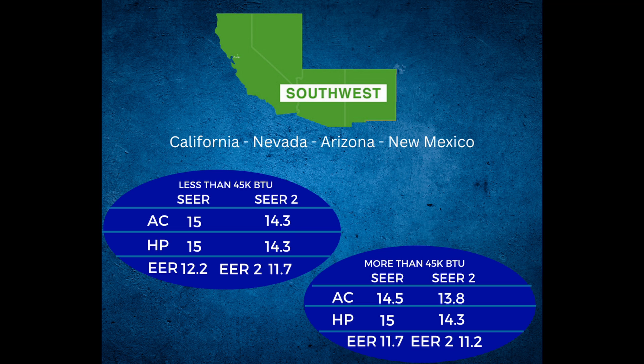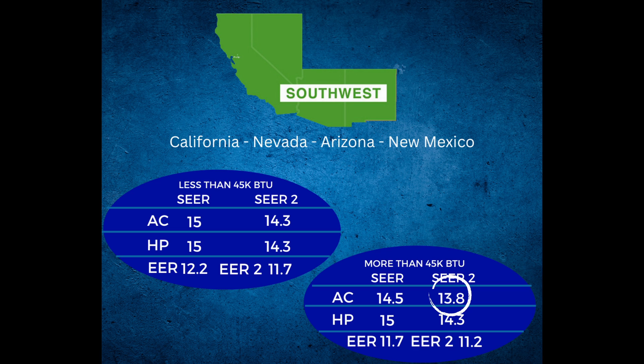Starting with air conditioning systems that are under 45,000 BTU, here are the numbers you need to know. For SEER 2, we're looking at 14.3 SEER 2. The SEER equivalent would be 15 SEER. And the EER number you're looking for is either 12.2 EER or, with the new EER 2, we're looking at 11.7. Moving on, if your equipment is greater than or equal to 45,000 BTUs, you're in a different category — 13.8 SEER 2 or 14.5 SEER, and for EER, we're looking at 11.2 EER 2 or 11.7 EER.